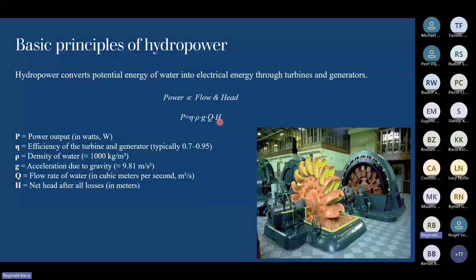If you take all of those losses and take them off the static or gross head, then you have your net head, and the net head times the flow in this formula is how you calculate your power. So really very basic engineering 101. In terms of head, if you classify or compare hydropower facilities, you've got high head plants and low head plants. I guess you can sneak in medium head plants in here, but typically we refer to high head and low head. So let's take a bit of time and talk through these types of hydropower plants.